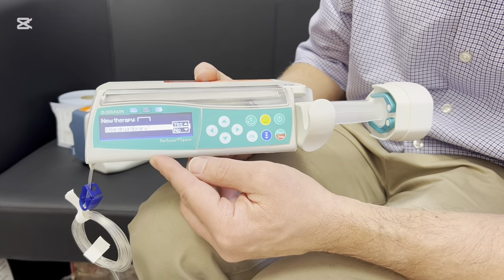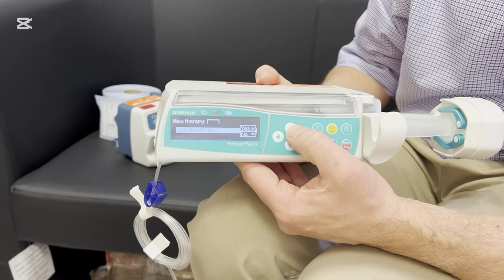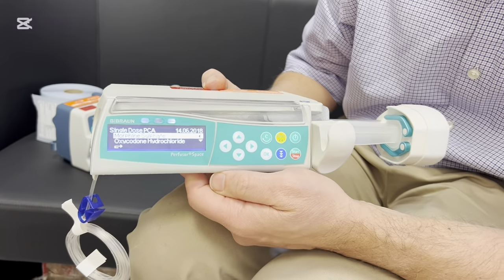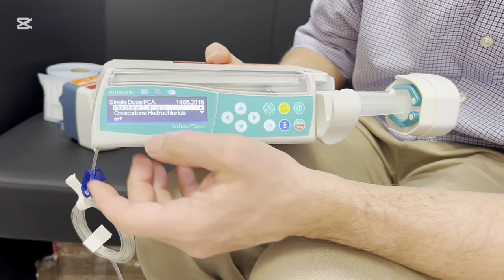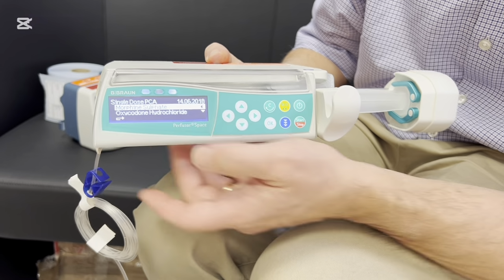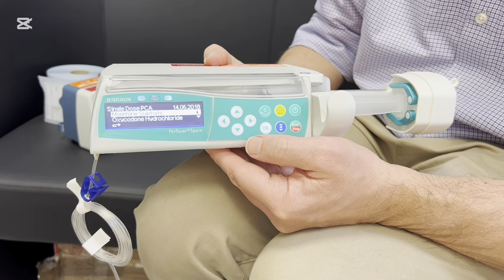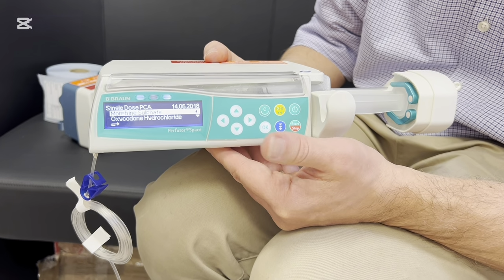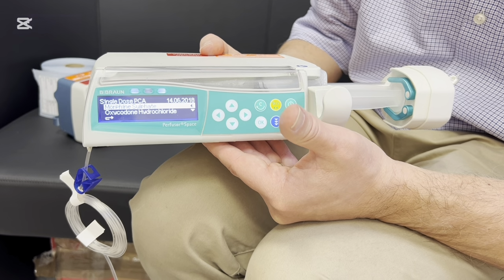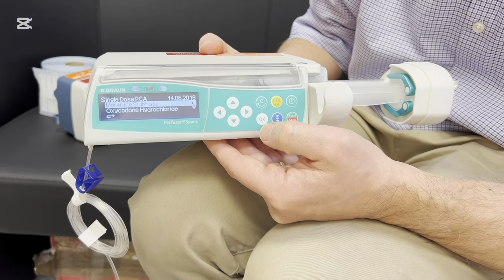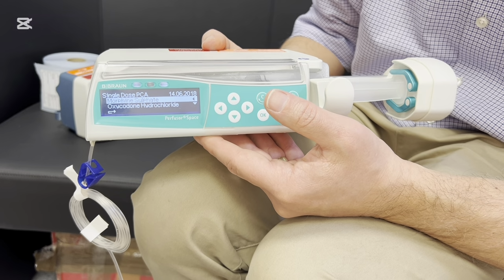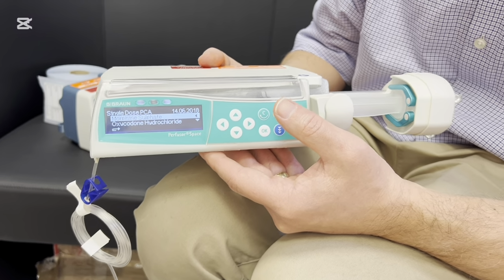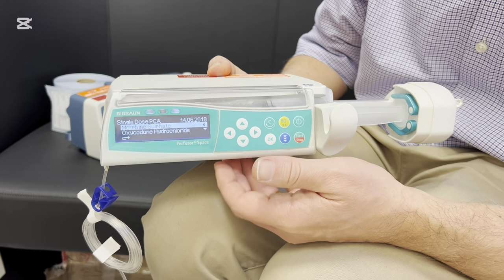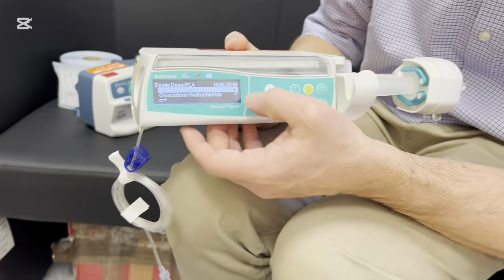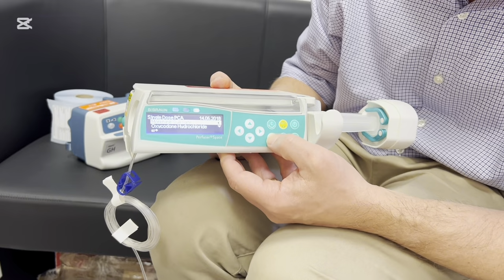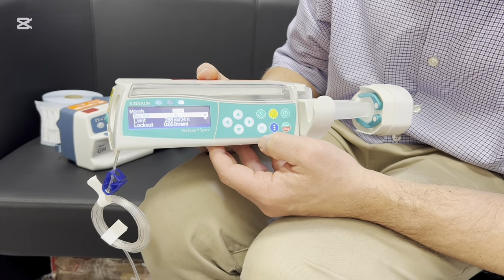It asks, do you want to use the drug library? We're going to use this as a PCA pump, so we say yes, and then you can select whether to use morphine or oxycodone. And what you'll see up here is that this is a single dose PCA pump. So if you've got a patient receiving inadequate analgesia from a single dose PCA pump, the only other option is to change it to a double dose PCA pump. We haven't opened up the programming on this to allow you to change rates on the ward. It's just left purely as a single dose. So we're going to say morphine, and press OK.